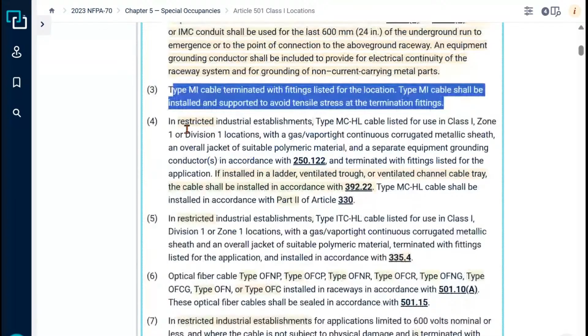But also what you'll notice is that there are some allowances down here for flexibility, okay? We're not really going to cover those, but it says if flexibility is necessary to minimize the transmission of vibration from equipment. So let me explain it. You have your wiring methods for a Class 1 Division 1, you're running it, but you may have a specific application where you need flexibility to some piece of equipment located in that environment. The code's got you covered. Maybe the rigid stops and you need some type of flexibility over to the equipment, whatever it be, the utilization equipment in that location. So we have some provisions for flexibility.